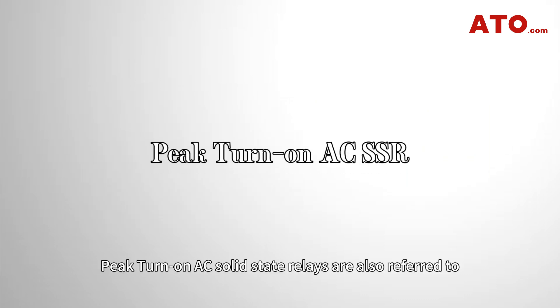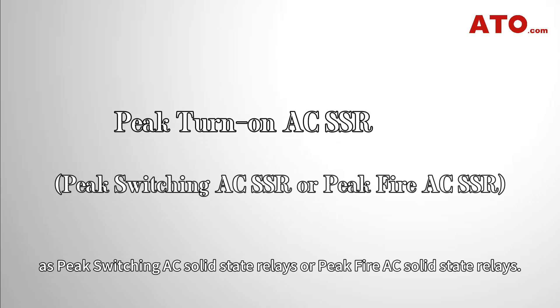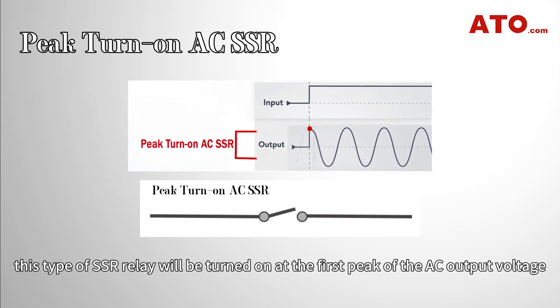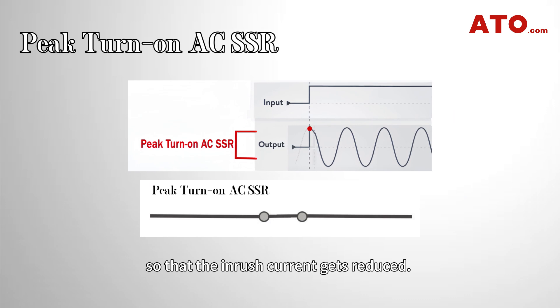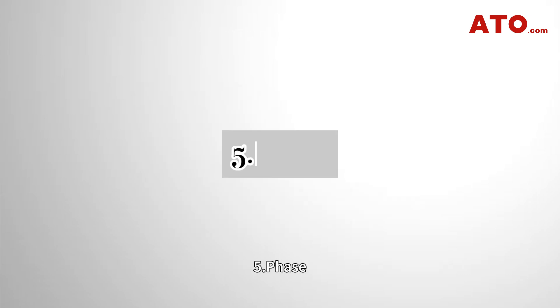Peak turn-on AC solid-state relays are also referred to as peak switching or peak fire AC solid-state relays. When the input control signal is applied, this type of SSR will be turned on at the first peak of the AC output voltage, so that the in-rush current gets reduced. If the input control signal is removed, the relay will be turned off.